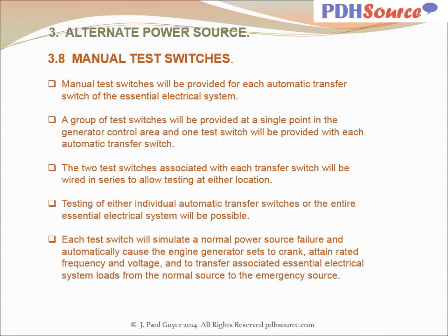Manual test switches will be provided for each automatic transfer switch of the essential electrical system. A group of test switches will be provided at a single point in the generator control area, and one test switch will be provided with each automatic transfer switch. The two test switches associated with each transfer switch will be wired in series to allow testing at either location. Testing of either individual automatic transfer switches or the entire essential electrical system will be possible.